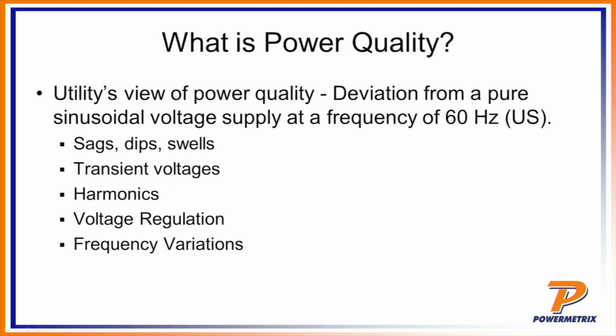So if we switch gears and we say, okay, we're going to look at this from the utility's point of view, what really is that definition of power quality from the utility's point of view? We define it as a deviation from a pure sinusoidal voltage supply at a frequency of 60 hertz. In an ideal world, the utility should be putting out a perfect sine wave that has no harmonics, no distortions of any kind, at a perfect frequency of 60 hertz.